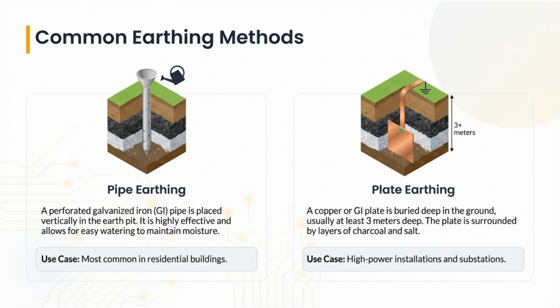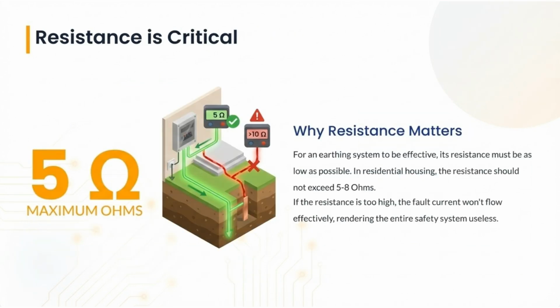Two common methods are pipe earthing, often used in residential buildings, and plate earthing, used for high-power installations and substations. Resistance is critical. For an effective system, resistance must be as low as possible, ideally not exceeding 5 to 8 ohms in residential housing. If resistance is too high, the safety system is useless.